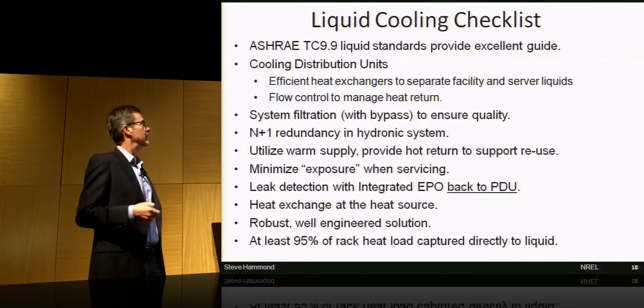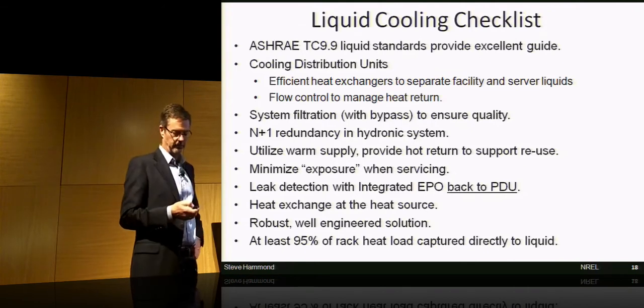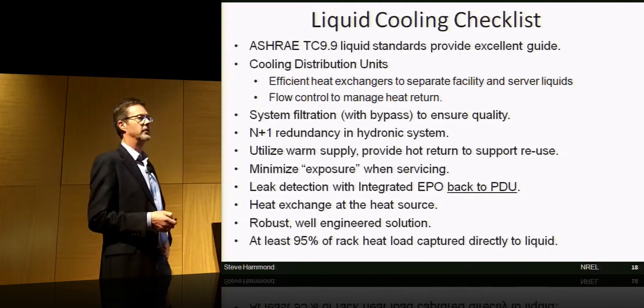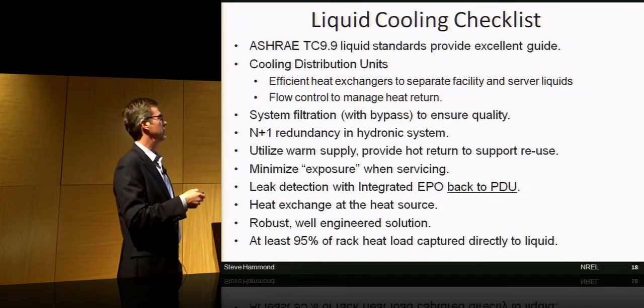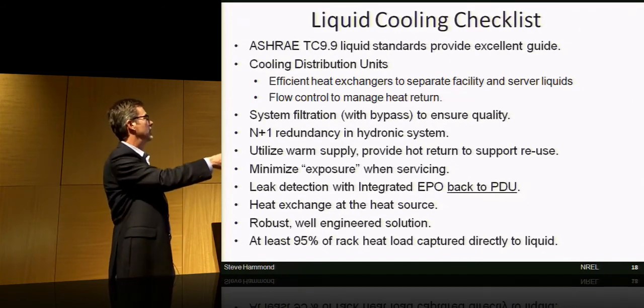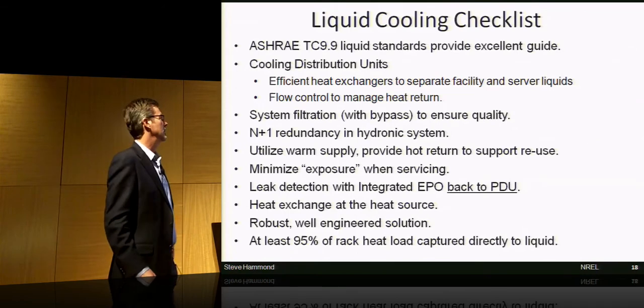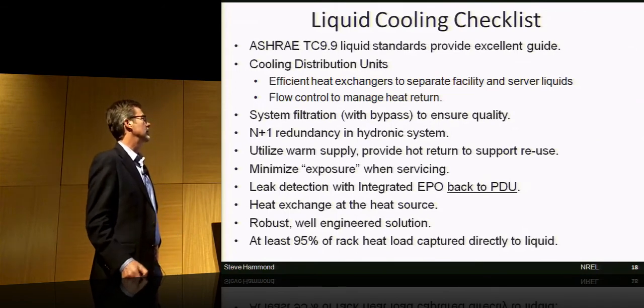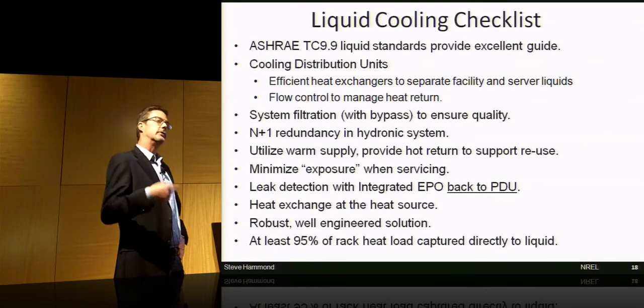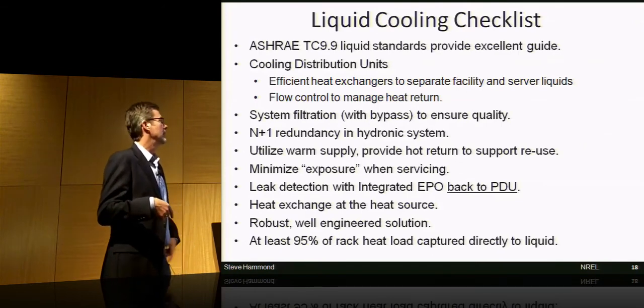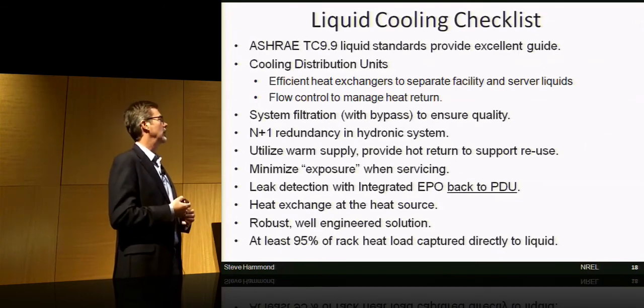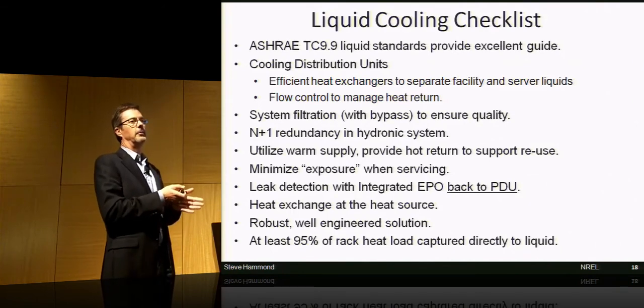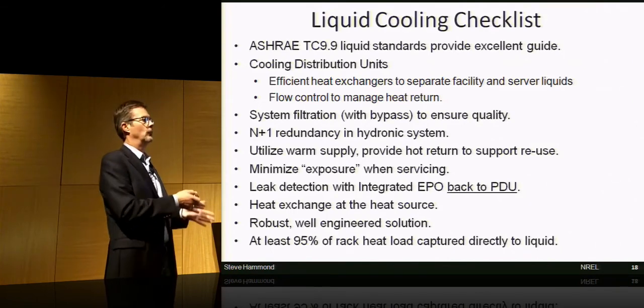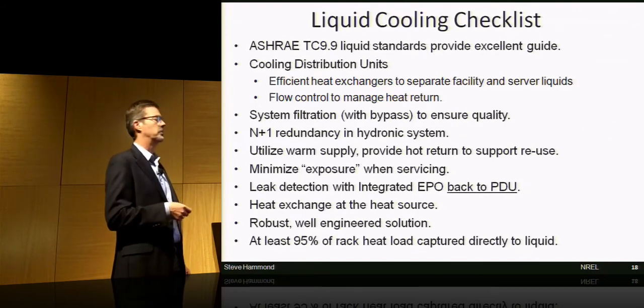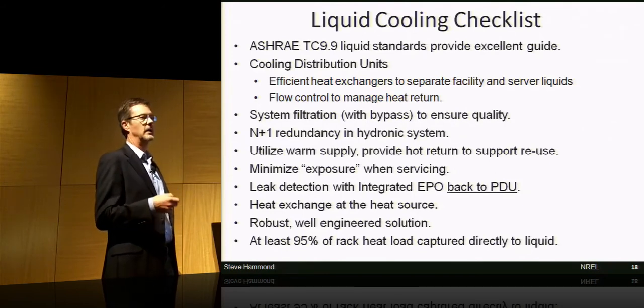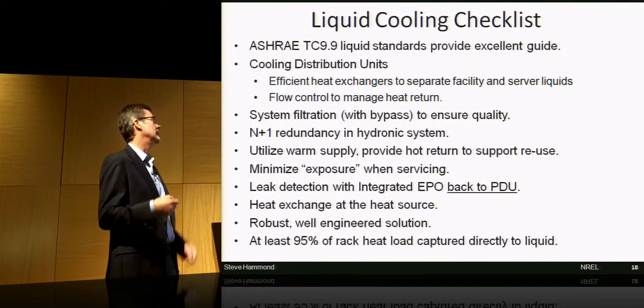So we have a liquid cooling checklist that we talk about with visitors and others that are interested, starting with: follow the standards. The ASHRAE guidelines provide an excellent guide if you're looking at liquids. We use in-row cooling distribution units. Those are very efficient ways of managing the heat load and to separate your building water and what water circulates among the racks. It also provides flow control to manage the temperature of the heat that's returned in your water.